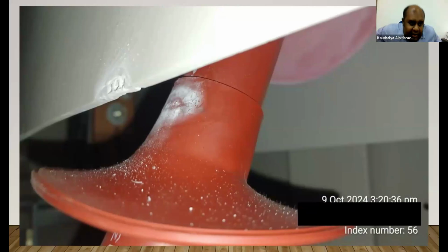So, solutions if you find it: there's a new installation, maybe a couple of years, less than 5 years, and because of poor installation work, it has developed. And yes, you can apply some silicone based paints, but for a limited time. You'll have to redo the cabling work for a proper installation, and that will incur another cost. If you fail to do your frequent maintenance, you never will know you have partial discharge until you hear hissing sounds there at your MV switchgear panels. Ultimately, a blast there at your MV switchgear panel.